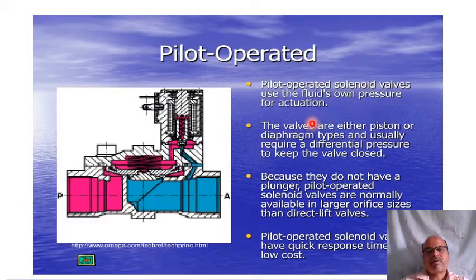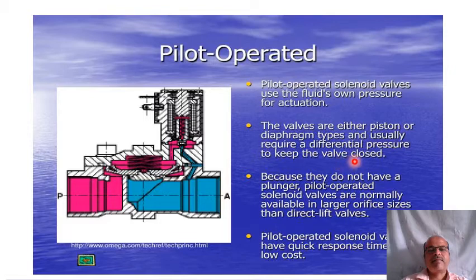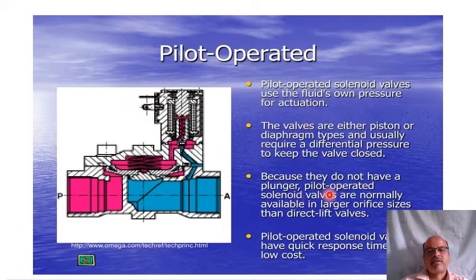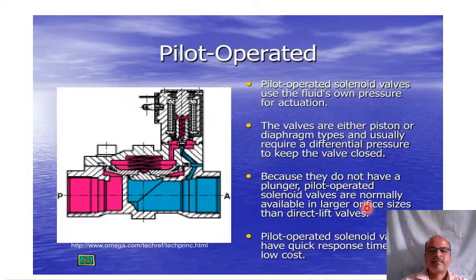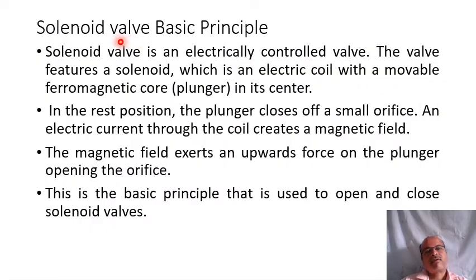Pilot operated solenoid valves use the fluid's own pressure for activation. The valves are either piston or diaphragm type and usually require a differential pressure to keep the valve closed. Because they do not have a plunger, pilot operated solenoid valves are normally available in larger sizes than directly operated valves.